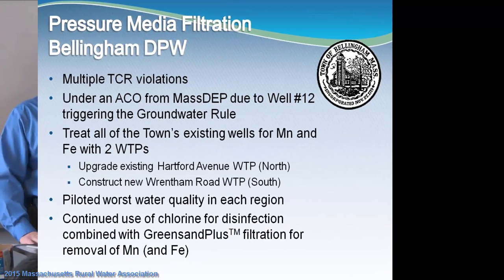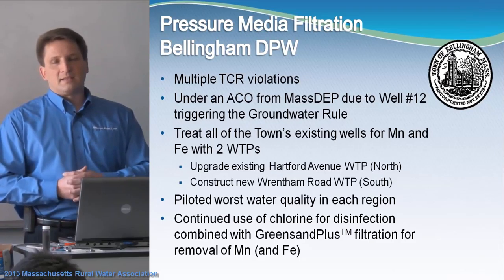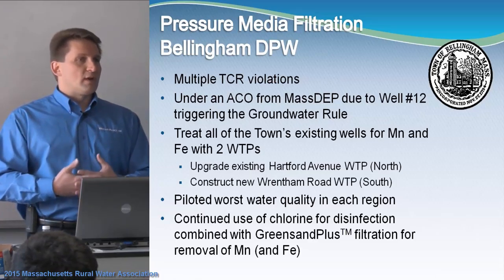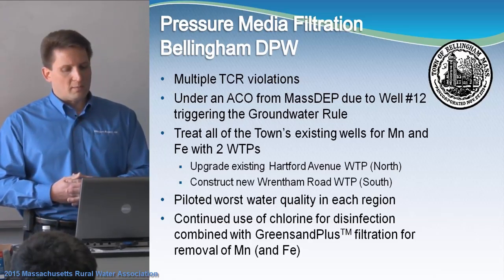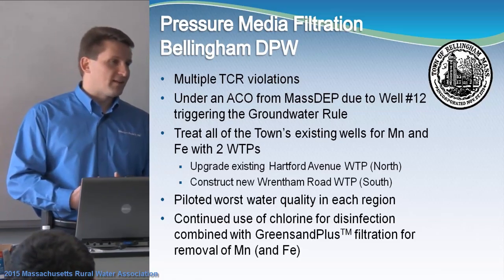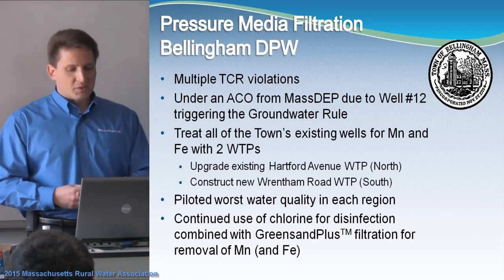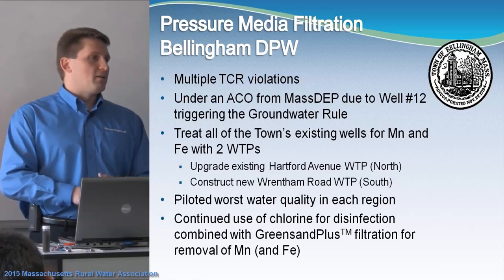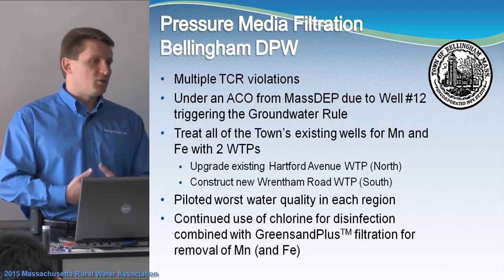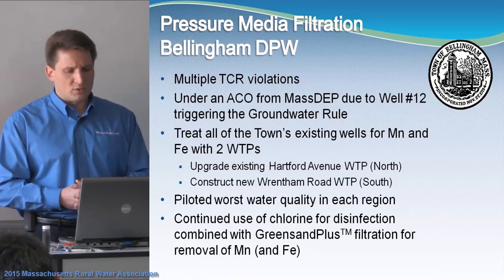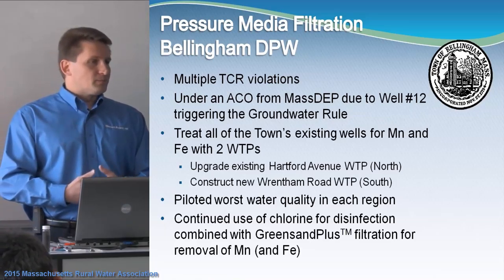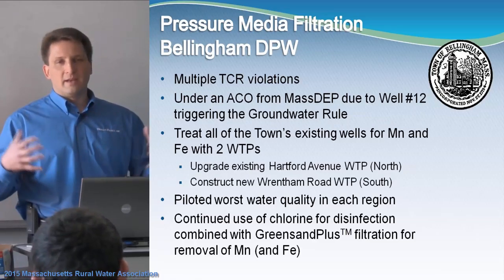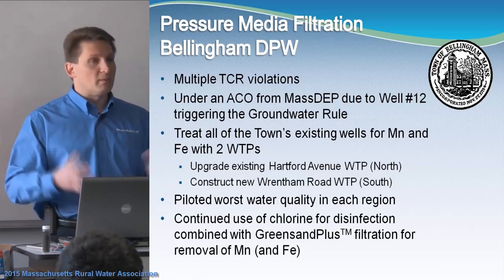Another project I'm currently working on is the town of Bellingham, Massachusetts DPW. They had significant total coliform rule violations and decided to start disinfecting on their own. Their well number 12 was triggered by the groundwater rule, requiring four-log viral inactivation, so they went permanent with chlorine disinfection. But chlorine with iron and manganese in the water — if you don't remove them first — creates that black mess, and they had significant consumer complaints throughout the distribution system. We were hired to study the system: could they use new sources, do interconnections, sequester, or treat? It boiled down that the most cost-effective solution was treatment for the entire town.